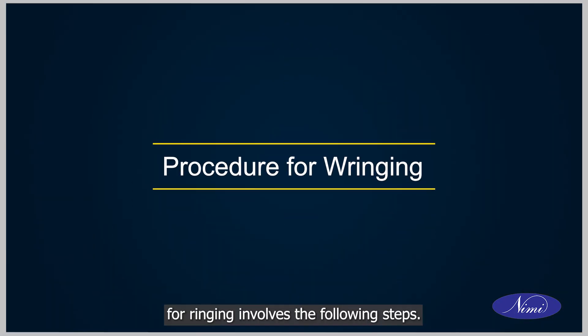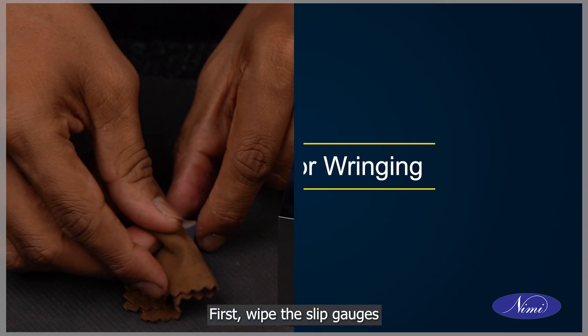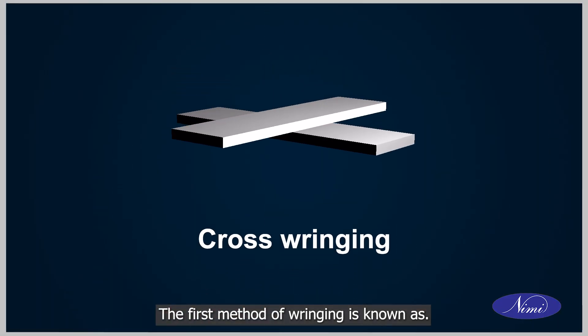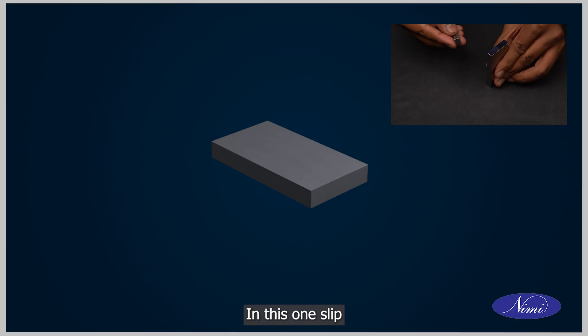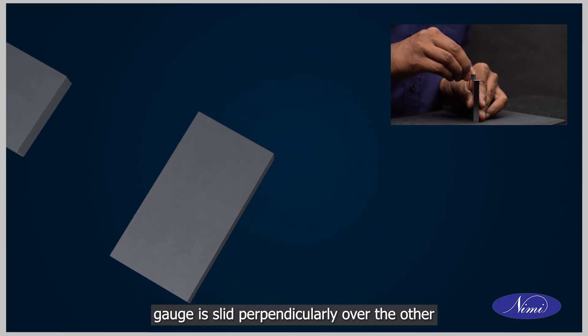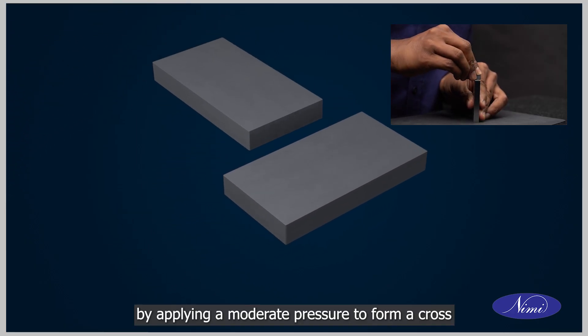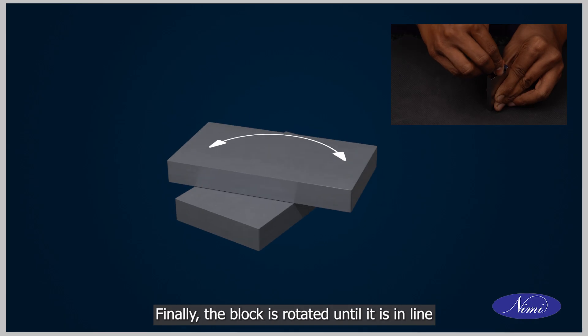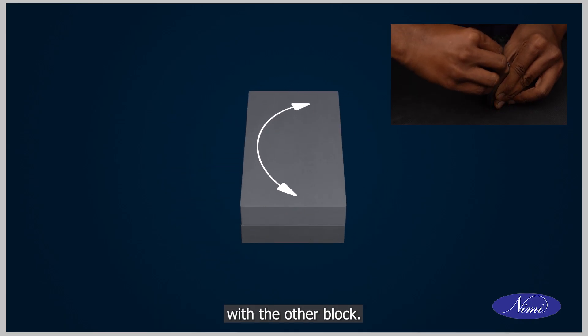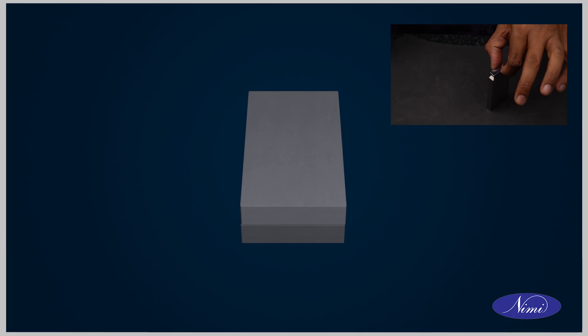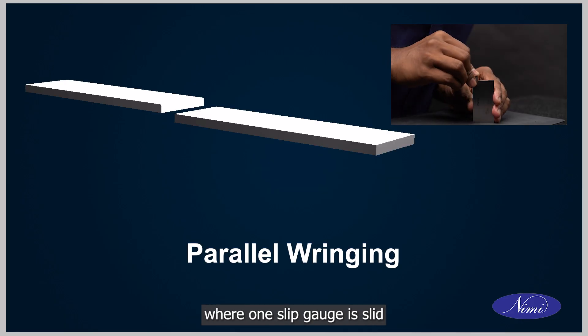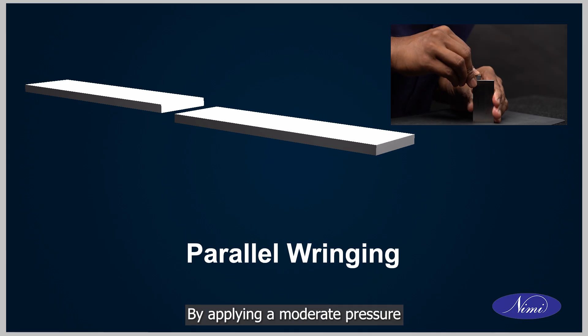The procedure for wringing involves the following steps. First, wipe the slip gauges with a clean chamois leather cloth. The first method of wringing is known as cross wringing, where one slip gauge is slid perpendicularly over the other by applying moderate pressure to form a cross or plus shape, and then the block is rotated until it is in line with the other block. The second method is parallel wringing, where one slip gauge is slid parallel over the other by applying moderate pressure.